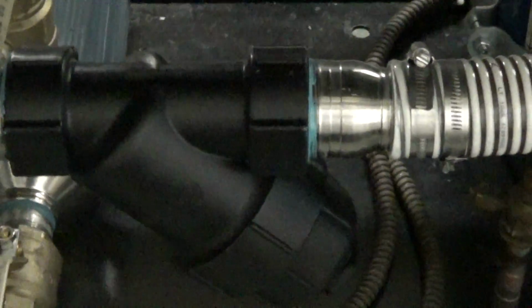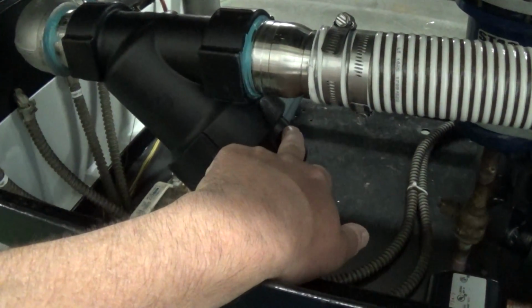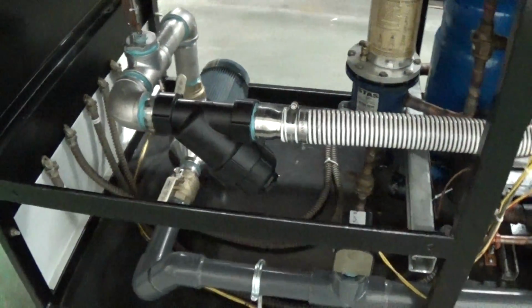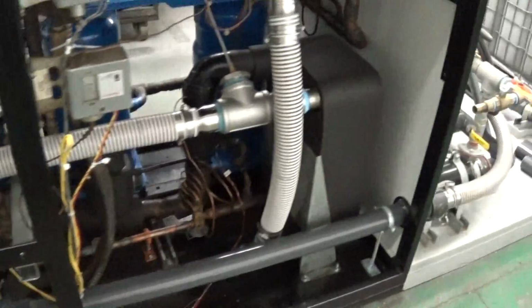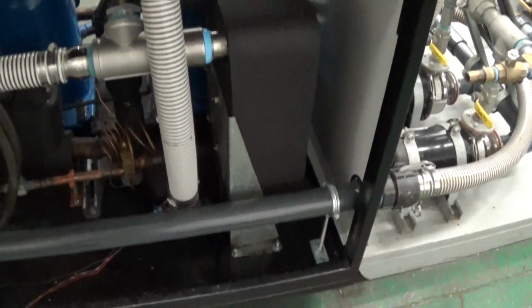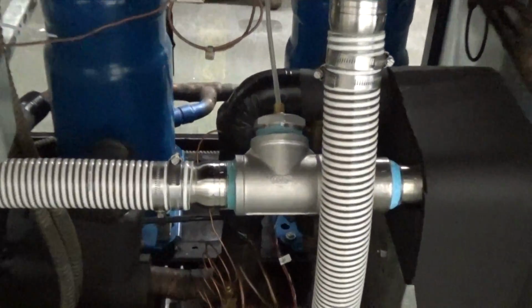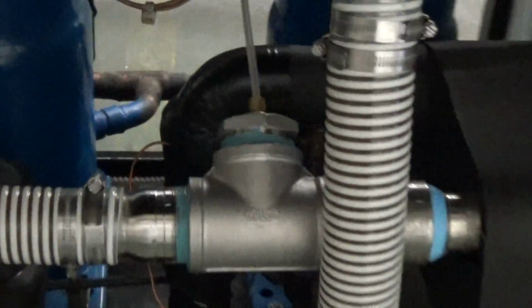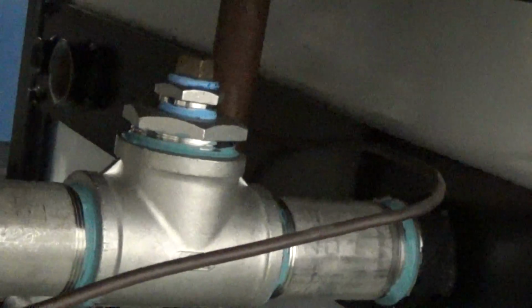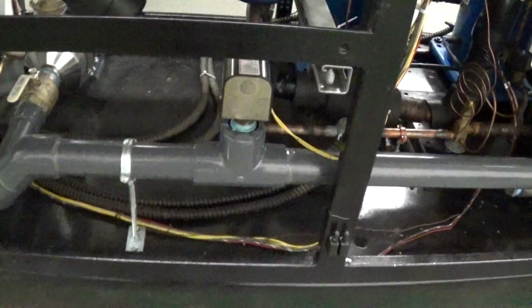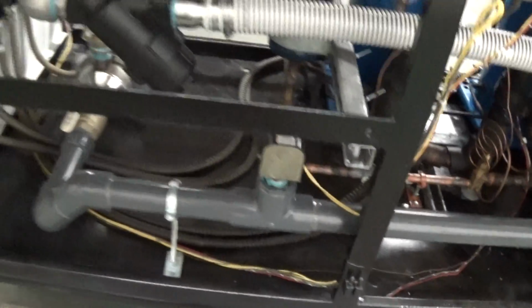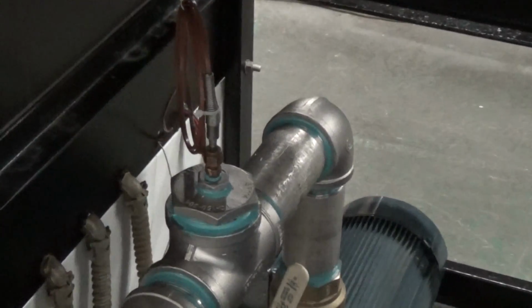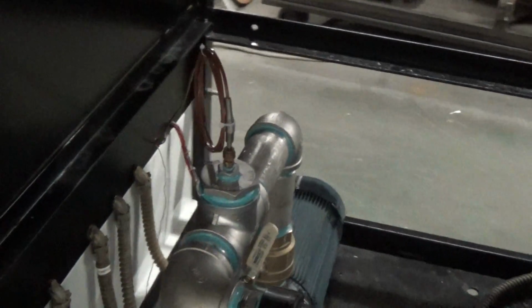We have a brand new Y strainer, which here, if you take this out, has what they call a 20/20 mesh screen that should be checked regularly. We flushed and cleaned the heat exchanger and put new insulation on it. We have this new fitting here, which goes to the pump pressure gauge. We have this pressure fitting up here. And here we have our flow switch, which senses our flow. And this here is our temperature sensor, which goes back to the controls.